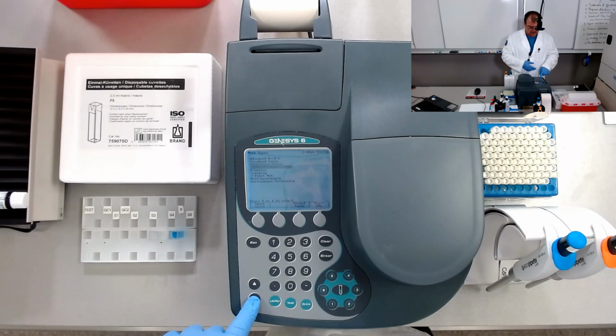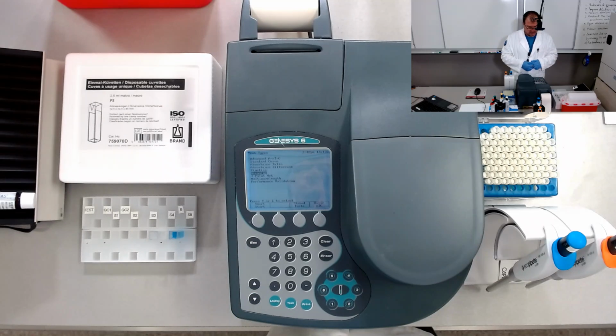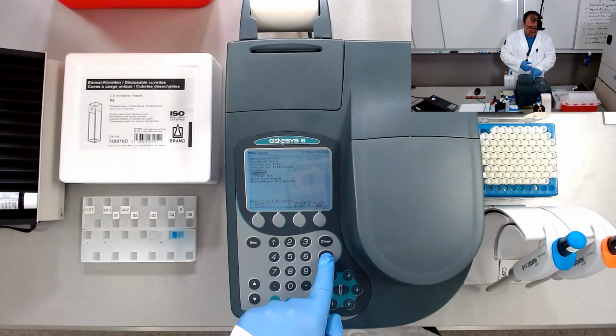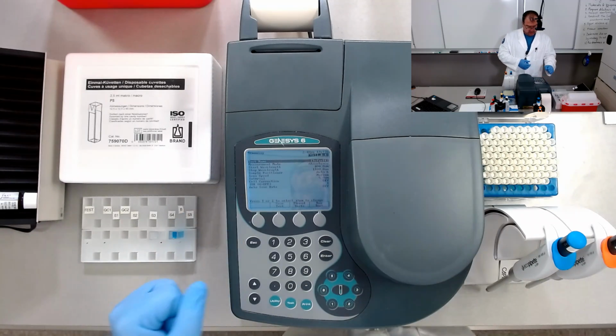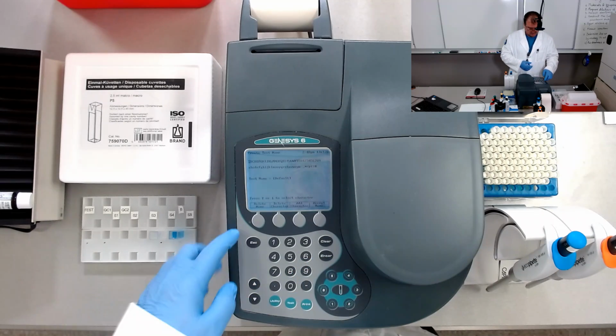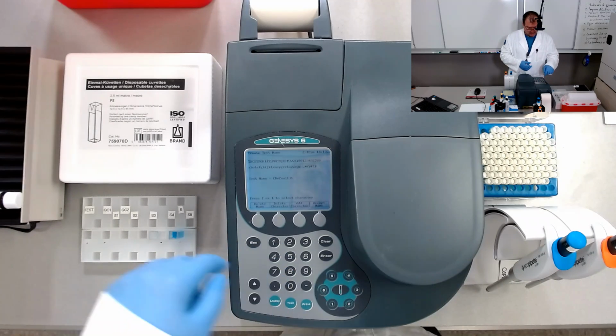scanning. In the scanning test, we are going to get the absorption spectrum. So in scanning here on the Genesys 6 spectrophotometer, we'll have the name for the test.